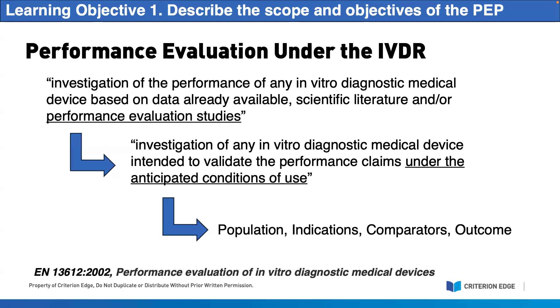So as you're beginning your performance evaluation, the PEP should be constructed to allow the evaluator to correctly perform and appropriately report on the performance evaluation overall. So a proper PEP should cover at least these aspects. So details on the intended purpose or intended use, the performance specifications of the IVD as established by the manufacturer, basically to ensure that that intended purpose is actually being fulfilled.